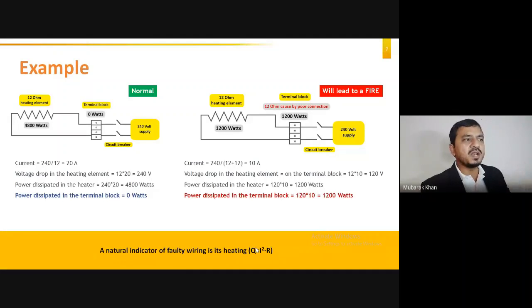Under normal conditions, 240 volt power supply will be supplying directly to the heating element. The resistance of the heating element is 12 ohm, so the power dissipated in the heater will be 4,800 watts. No issues, everything is okay. The power dissipated in the terminal block will be 0 because there is no resistance there, and the power dissipated in the circuit breaker will also be equal to 0 because there is no resistance there.